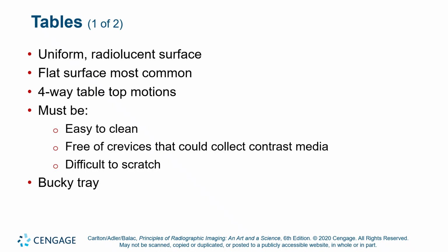It must be easy to clean, so let's not do a textured pattern. Let's just do a flat countertop-like surface, because textured patterns, while they'll probably hold the patient to the table a little bit better and prevent some of those falls, are also going to be fomites. So any textured surfaces are right out, because the cracks and crevices of the texture are going to hold on to your MRSA, your VRE, your rhinovirus, and basically any of the infectious pathogens your first patient brings in.